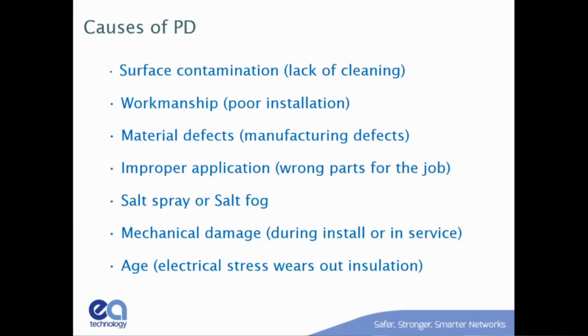We see a lot of workmanship problems. And then age. As things do get old, things dry out and things wear out and plastic gets brittle. So you see stuff in the 30 to 40-year-old range is starting to have PD, even though it may not have had it for any other reason. Like I say, now we see a lot of cables installed in the last 10 to 20 years when they started coming out with cold shrink terminations.